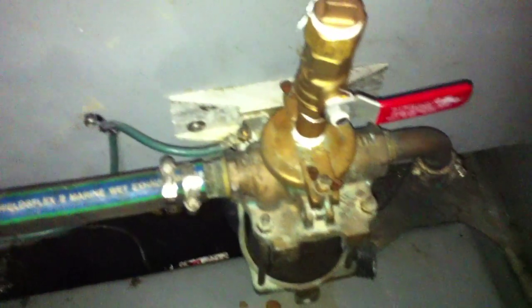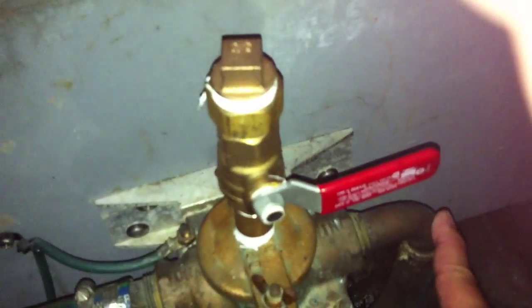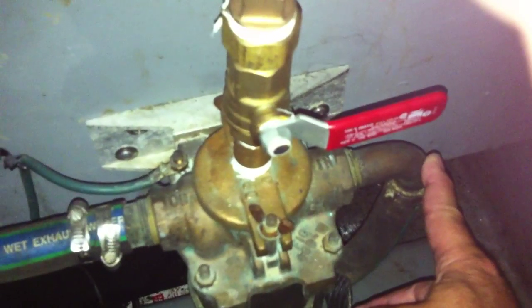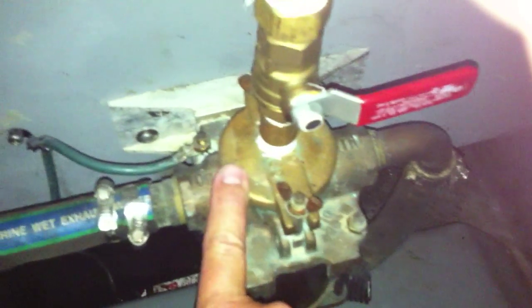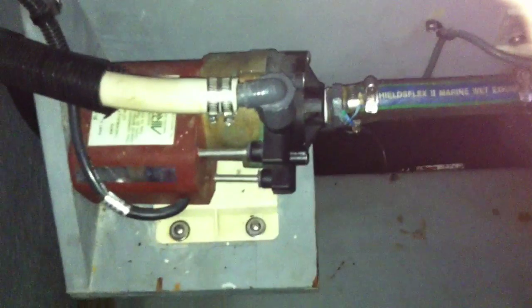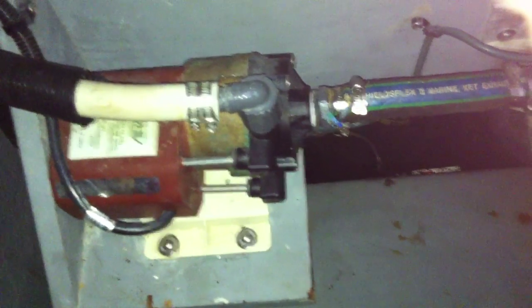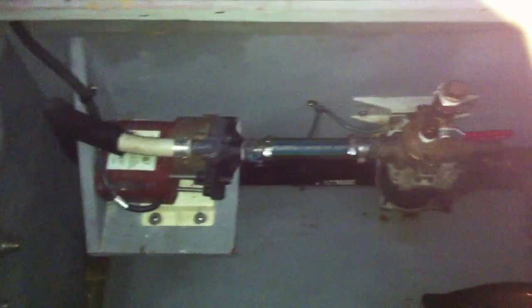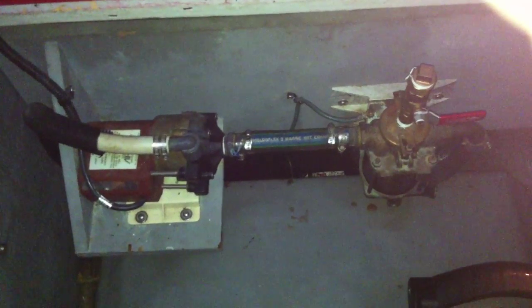Just below that is the sea strainer for the air conditioning. Let me show you—this is water coming up from the seacock on the bottom of the boat, the valve that lets water in. It runs through the strainer and back out to this pump, which sends it to the two air conditioning units in the boat, cooling them. Or when we're in reverse cycle heat mode, the water brings heat to those units by pulling latent heat out of the water to create heat for us.